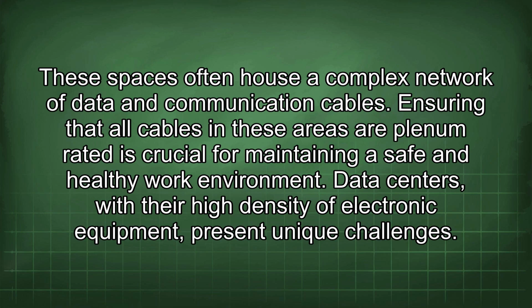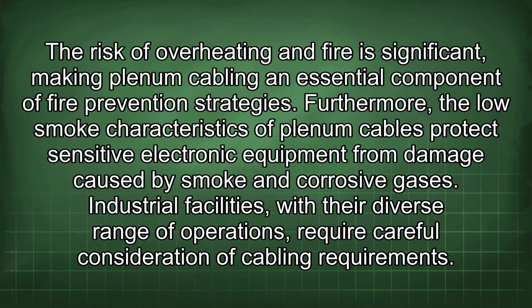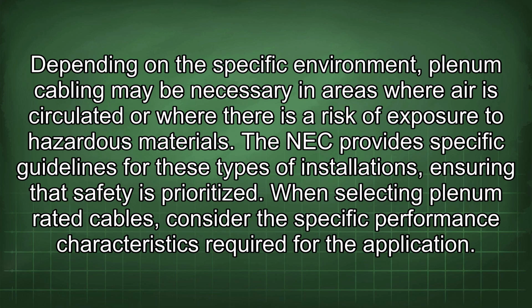Data centers, with their high density of electronic equipment, present unique challenges. The risk of overheating and fire is significant, making plenum cabling an essential component of fire prevention strategies. Furthermore, the low smoke characteristics of plenum cables protect sensitive electronic equipment from damage caused by smoke and corrosive gases. Industrial facilities, with their diverse range of operations, require careful consideration of cabling requirements. Depending on the specific environment, plenum cabling may be necessary in areas where air is circulated or where there is a risk of exposure to hazardous materials. The NEC provides specific guidelines for these types of installations, ensuring that safety is prioritized.